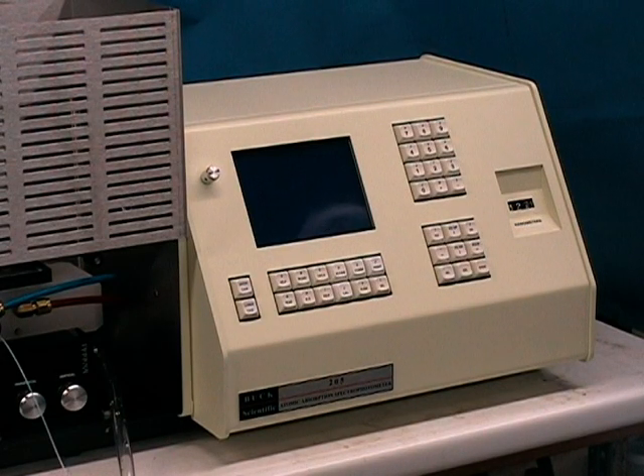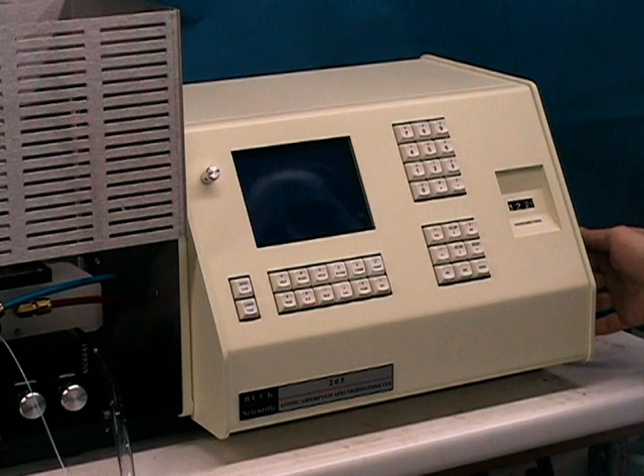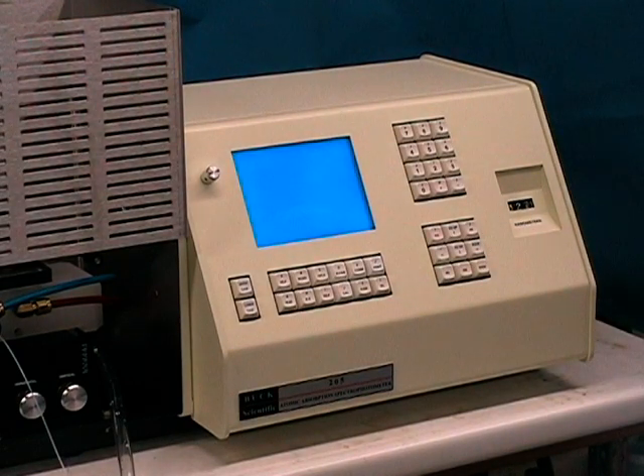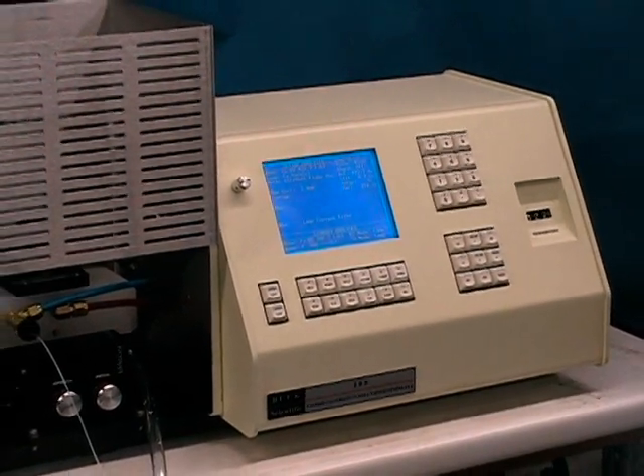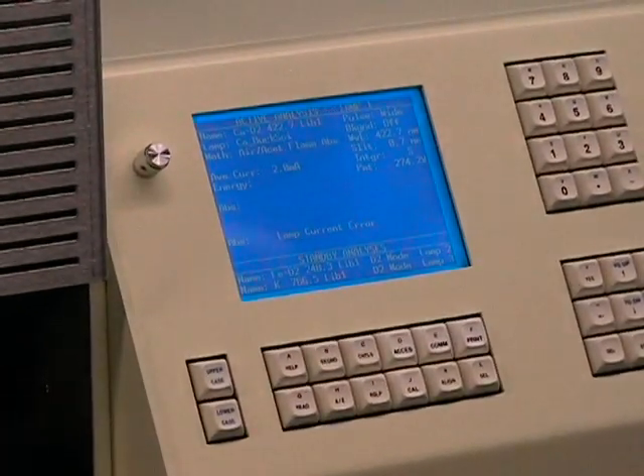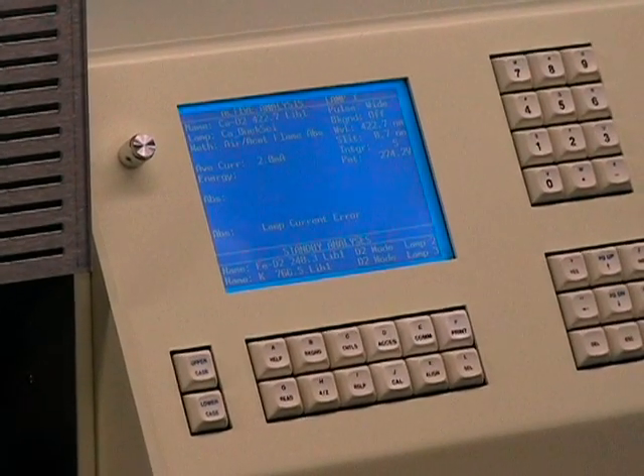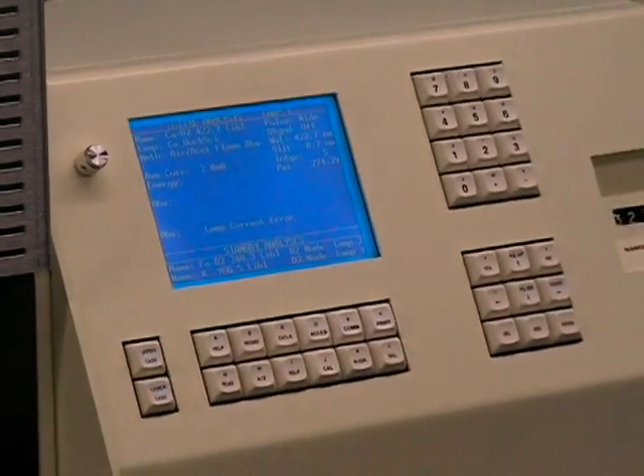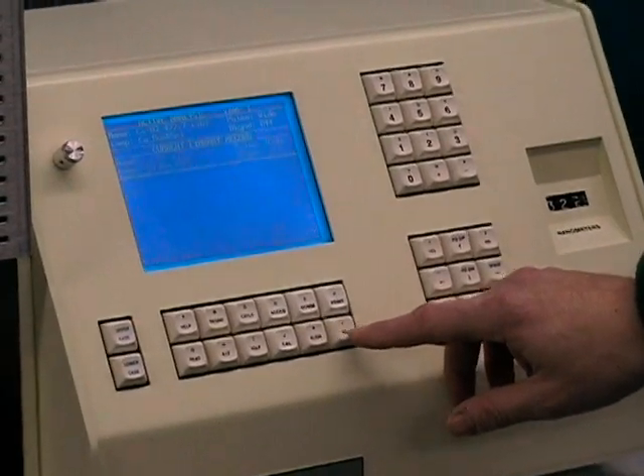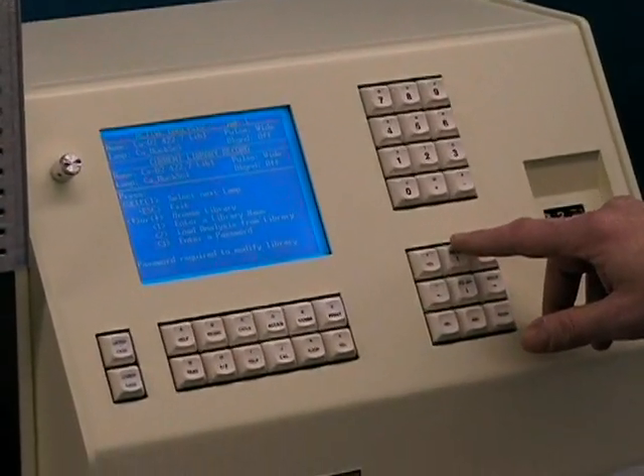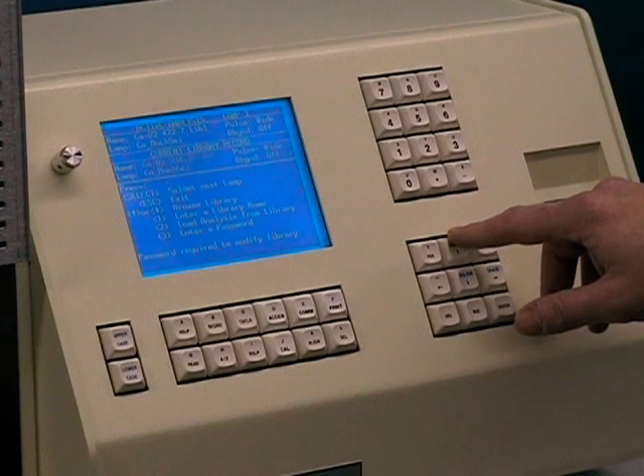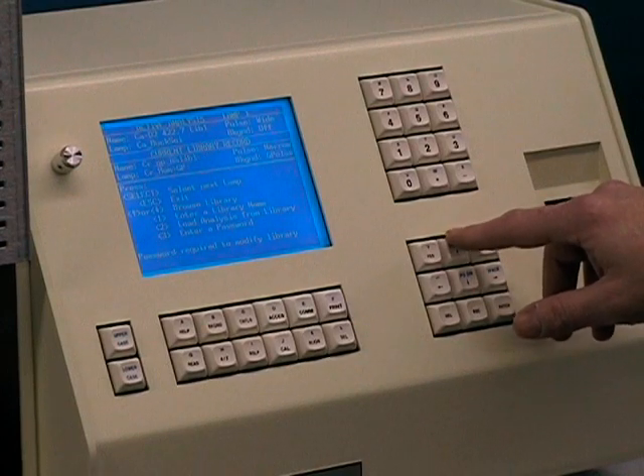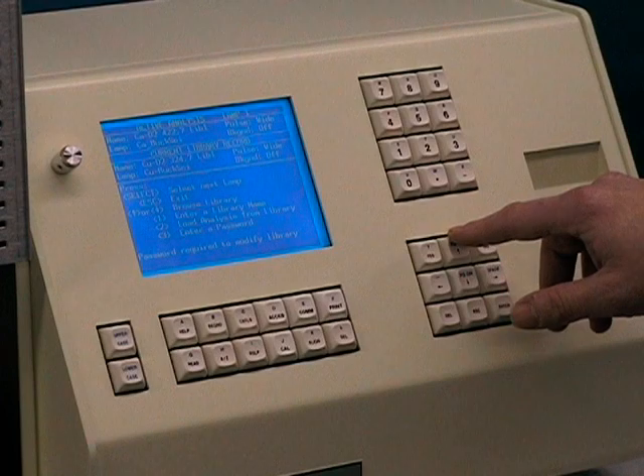Turn on the instrument by pressing the power button on the right side panel of the unit, and like any microprocessor-based system, wait a few moments for it to initialize and set itself up for display. The system displays the active analysis window, which is where all of your analytical information will be seen. To set up for an analysis, press the Select key, which will enter you into the library mode. And using the up and down arrows, select the elements you want for this particular lamp.